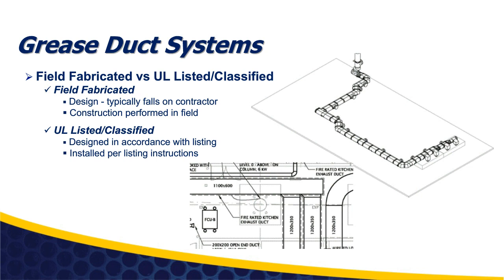On the UL listed label product, the design is going to be done in accordance with its listing. So horizontal hangers are going to be placed in positions that are part of the engineered testing that's done at UL. Vertical support is going to be done the same way. The constant monitoring by UL of our construction processes and fabrication processes are going to be adhered to when a product has a label on it. And then it's really easy from an installation standpoint on a factory-built product, when you have a drawing that is designed by us and has UL compliance to it, to easily inspect the system to ensure that it has the components in the right place and has all the integrity to meet the UL listing that it's designed for.